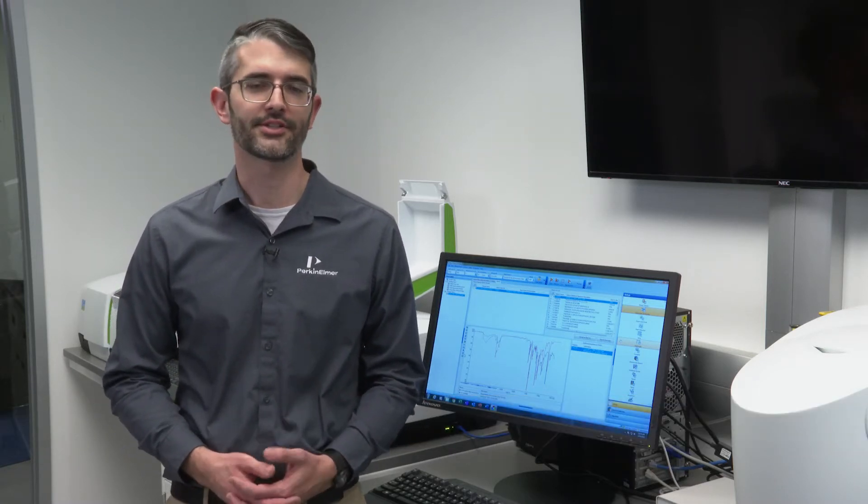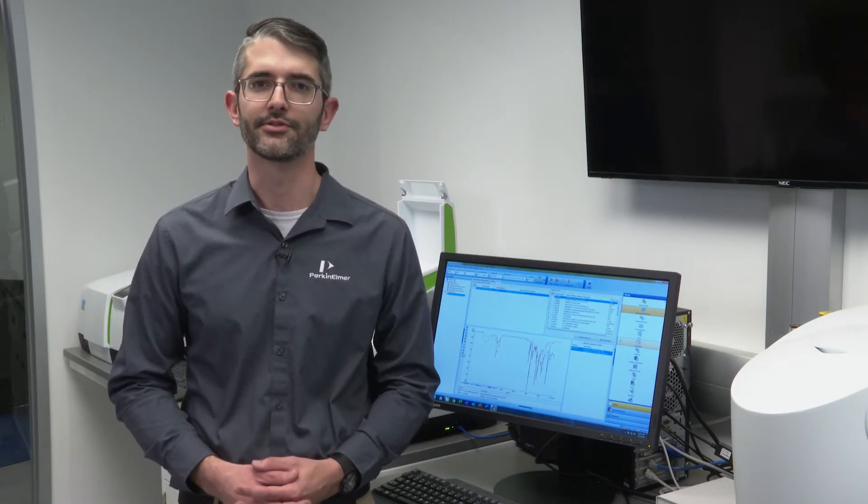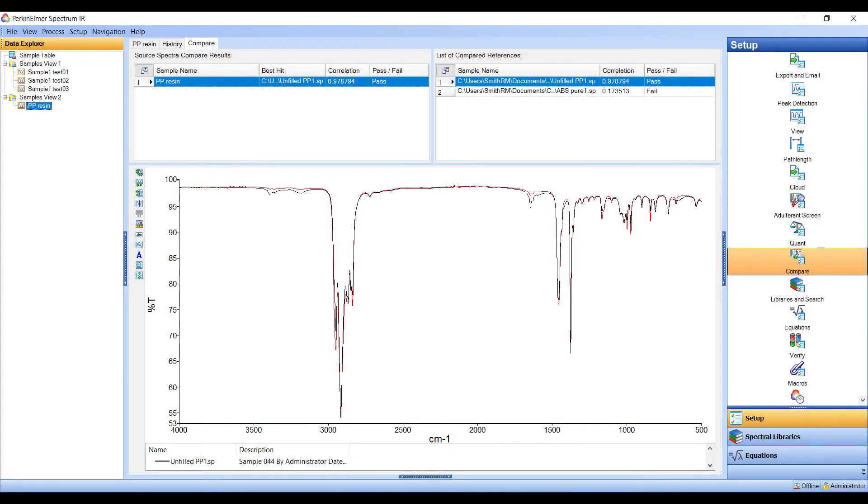If the material is one of several expected materials, such as a situation where the FTIR is being used for raw material identification, typically an algorithm such as Perkin-Elmer's Compare algorithm is employed.